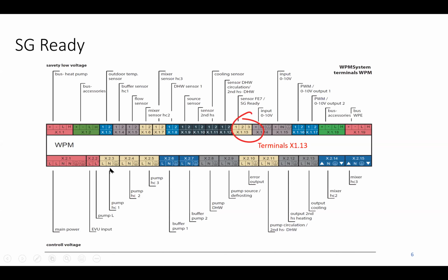Heating circuit number 1, being straight out of the tank and not mixed, would always be your hottest circuit, okay? So if you're going to do radiators, you put them into heating circuit 1. If you're going to do underfloor, you put them into heating circuit 2 and 3, okay? Not the other way around, because heating circuit 1 basically is straight out of the buffer tank. So if you're doing radiators and underfloor heating, you'd come straight out of the buffer tank with the hottest water to do your radiators, and obviously then you'd mix down to do your underfloor heating circuit. So what we do, we've covered this before, is put sensors on the heating circuits so we can measure what is going to 2 and 3.